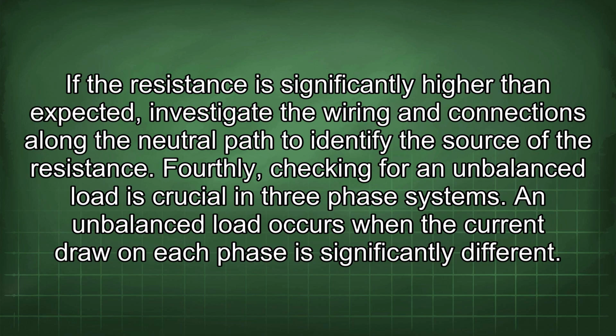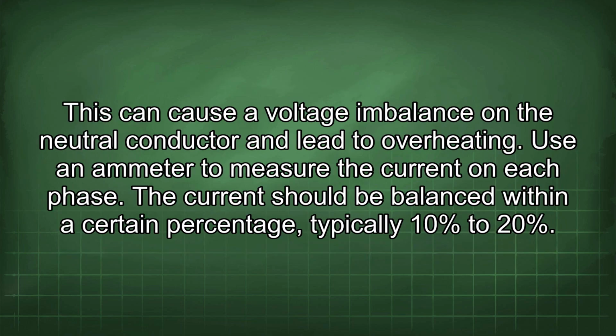If the resistance is significantly higher than expected, investigate the wiring and connections along the neutral path to identify the source of the resistance. Fourthly, checking for an unbalanced load is crucial in three-phase systems. An unbalanced load occurs when the current draw on each phase is significantly different. This can cause a voltage imbalance on the neutral conductor and lead to overheating.